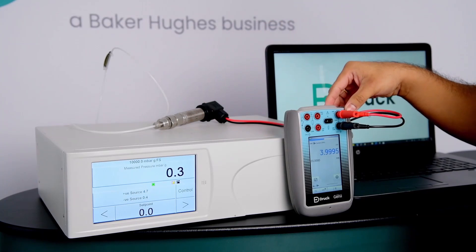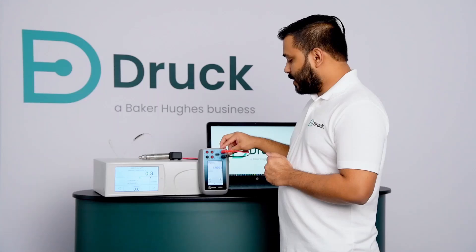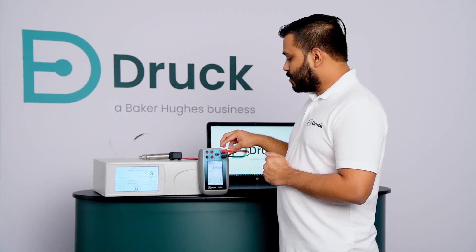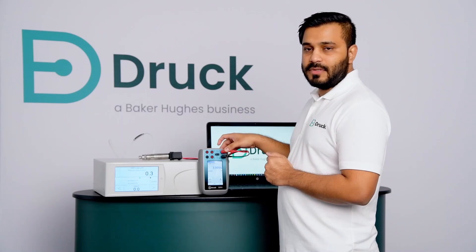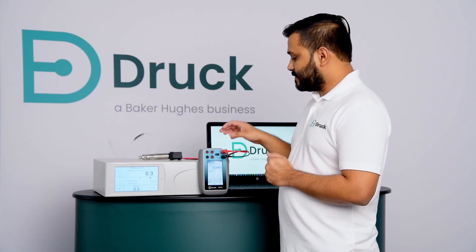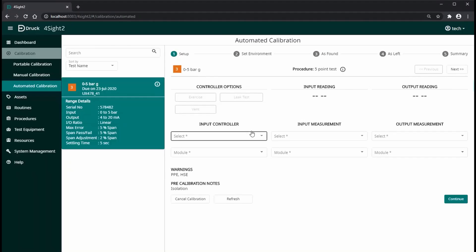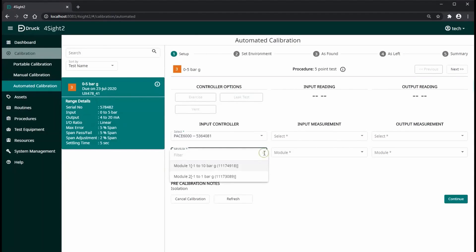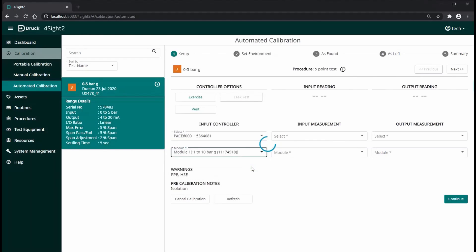For my output measurement, I have a DPI 620G multifunction calibrator and I am going to read milliamp output on this particular device. Unique 5000 sensor has been assigned for automated calibration and Pace 6000 and DPS620G are connected to my laptop via USB connection.